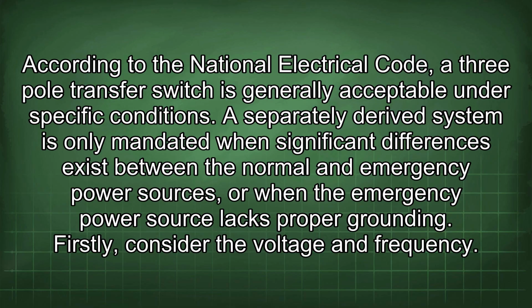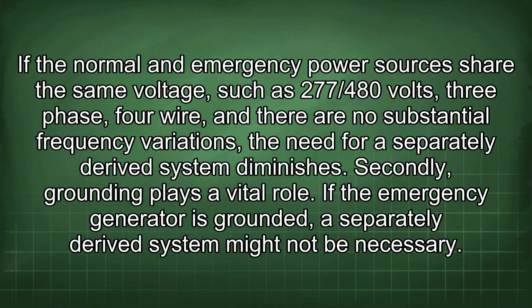According to the National Electrical Code, a 3-pole transfer switch is generally acceptable under specific conditions. A separately derived system is only mandated when significant differences exist between the normal and emergency power sources, or when the emergency power source lacks proper grounding. Firstly, consider the voltage and frequency. If the normal and emergency power sources share the same voltage, such as 277/480 volts, 3-phase, 4-wire, and there are no substantial frequency variations, the need for a separately derived system diminishes.